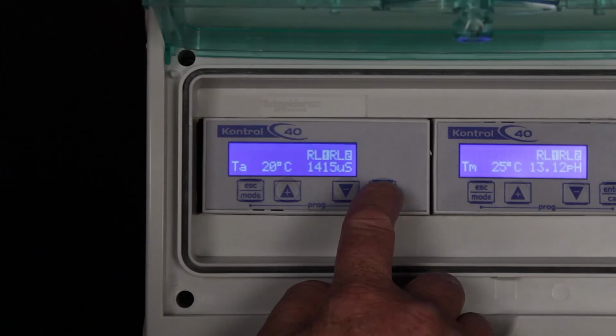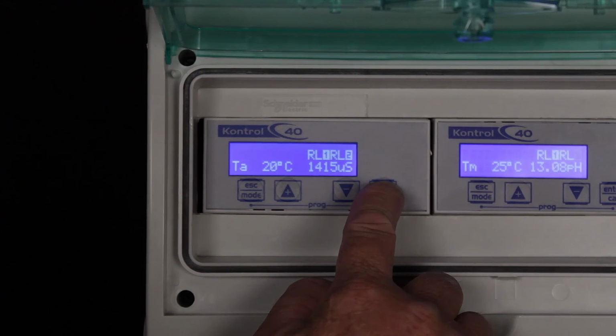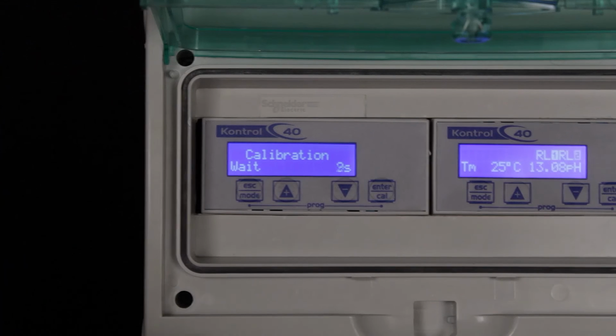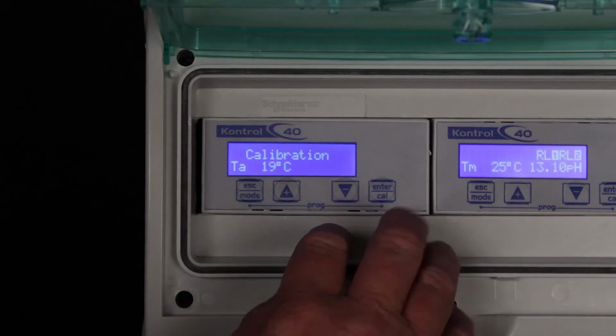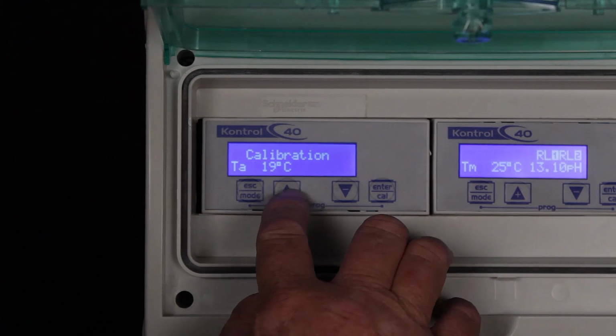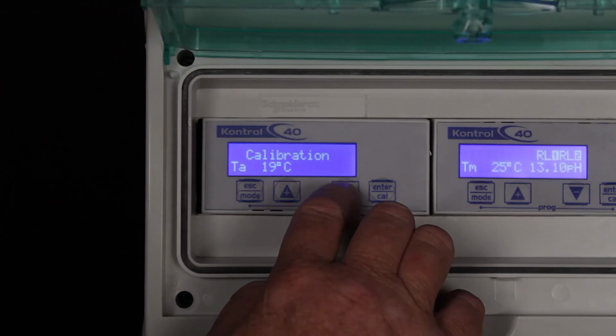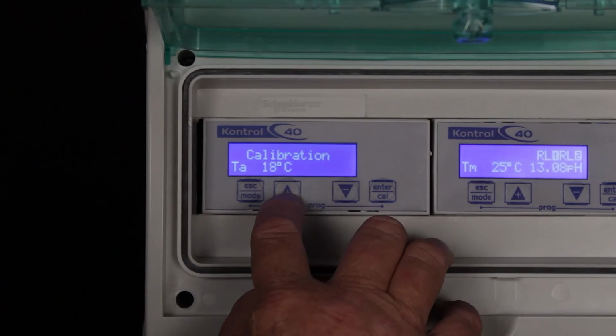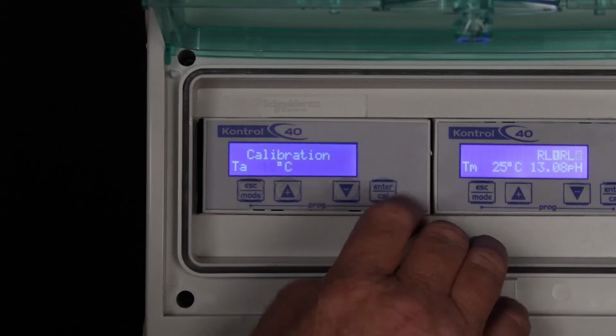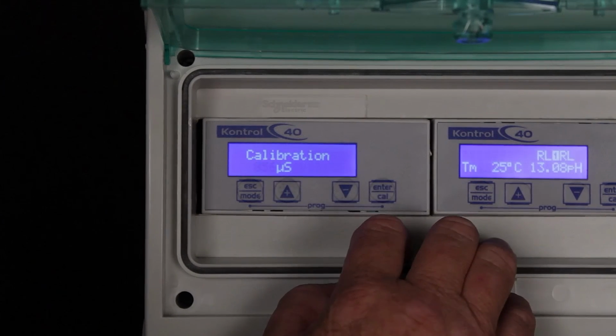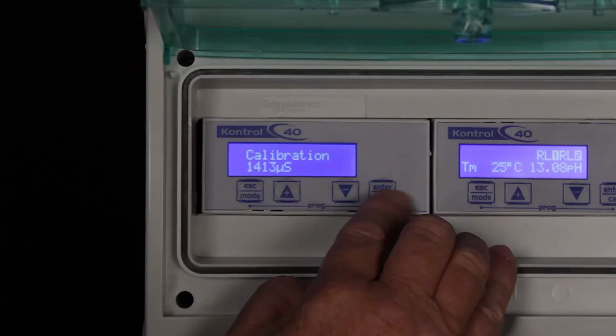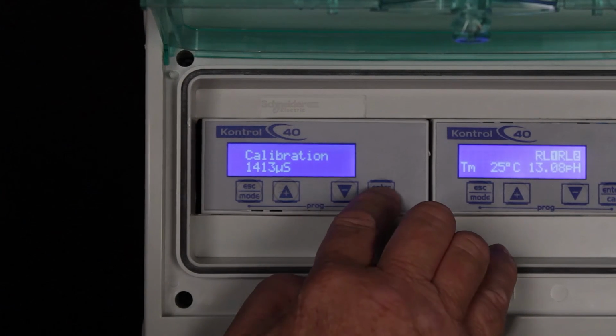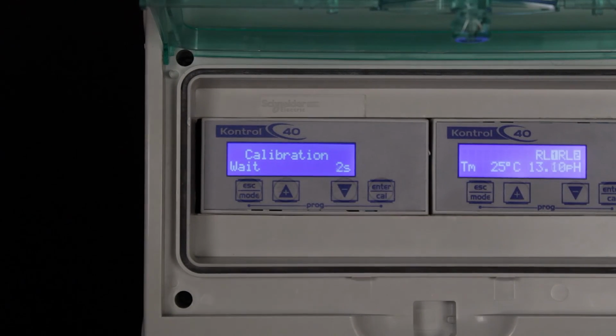Press and hold the enter calibrate button until the screen changes. Wait 10 seconds and the controller will indicate the temperature of the solution. If this needs to be corrected, you can manually change the temperature reading. Next, enter the buffer value. In this case, our buffer value is 1413 microsiemens. The controller will count down another 10 seconds and then you will have successfully calibrated the conductivity controller.